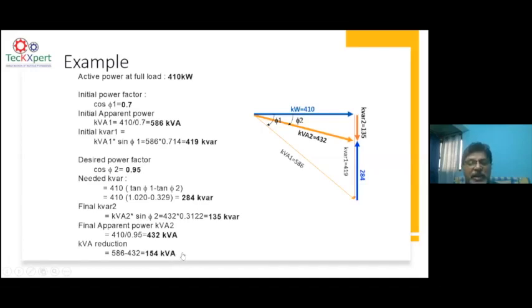That means when you put a capacitor bank and improve the power factor, it reduces the kVA demand on the transformer or on the grid, and that is why we have to make sure the consumers are always maintaining a good power factor, so that the losses are reduced at the transformer side or at the grid side. Even for a consumer running some generators, you can save that extra power on the generator or on the transformer, so that you can connect additional loads by improving the power factor.